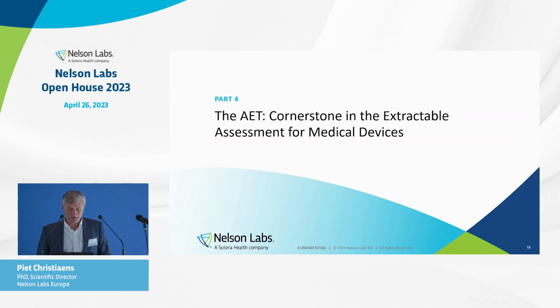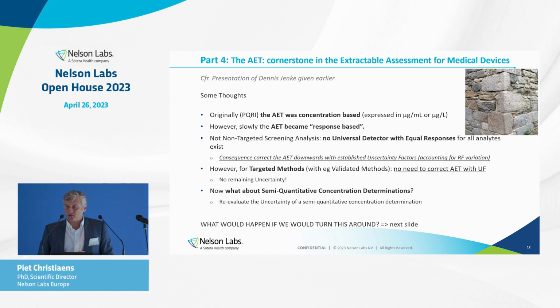For the AET, which is the cornerstone in the extractable and leachable assessment, it defines how low you need to go. There are some thoughts. So initially, when the concept of the AET was introduced by the PQRI working team, who wrote the recommendations for OINDPs, it was a concentration-based threshold. But slowly, we went to a response-based threshold. Now, when you're combining different methodologies, we know that the detectors are not universal, in a way that different compounds will have a different reaction or give a different response to each of the detectors. So because of that variation, you need to introduce uncertainty factors.